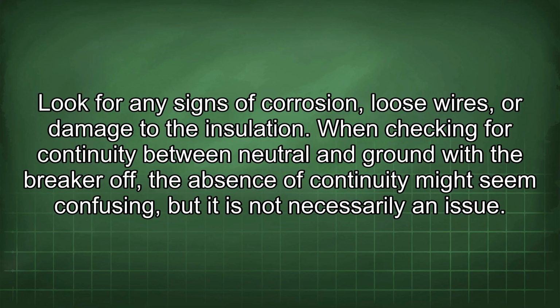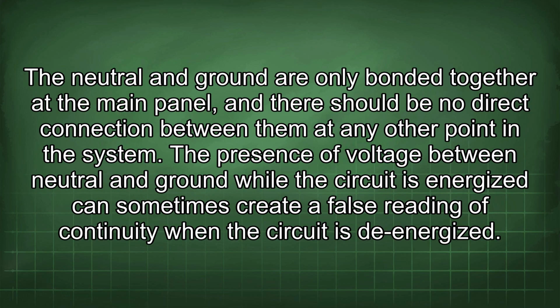When checking for continuity between neutral and ground with the breaker off, the absence of continuity might seem confusing, but it is not necessarily an issue. The neutral and ground are only bonded together at the main panel, and there should be no direct connection between them at any other point in the system. The presence of voltage between neutral and ground while the circuit is energized can sometimes create a false reading of continuity when the circuit is de-energized.